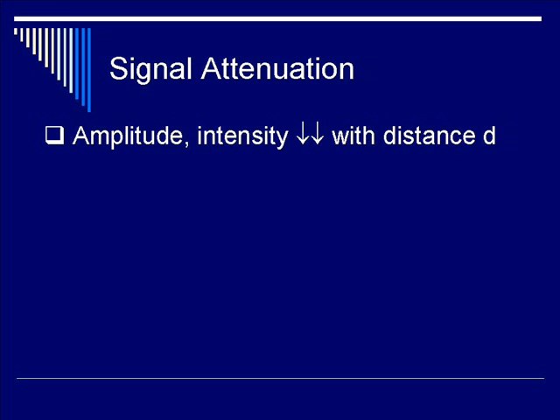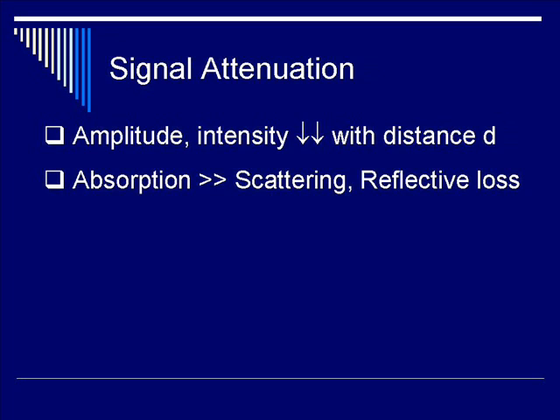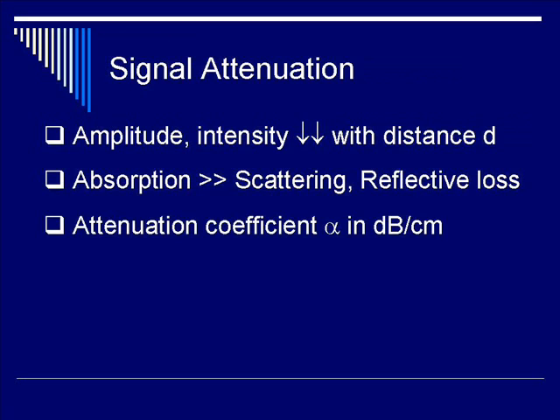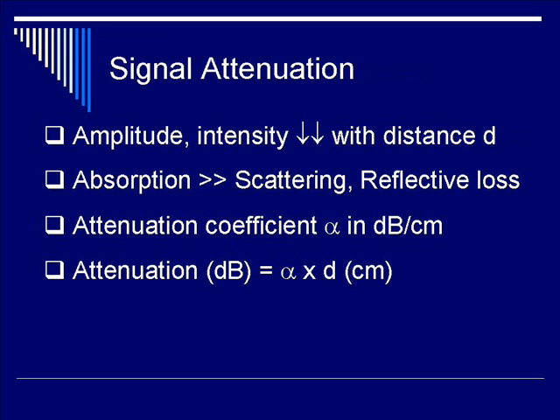Finally, we're going to talk about signal attenuation of ultrasound beams. Both the amplitude and intensity of the ultrasound beam decrease with distance D. Most ultrasound beam signal loss is due to absorption, which is significantly greater than the scattering or reflective loss component. The attenuation coefficient can be lumped for all three mechanisms into a single variable called alpha, in units of decibels per centimeter depth. Attenuation in its totality is measured as the product of alpha multiplied by the actual distance in centimeters, and the resulting unit for attenuation is decibels.